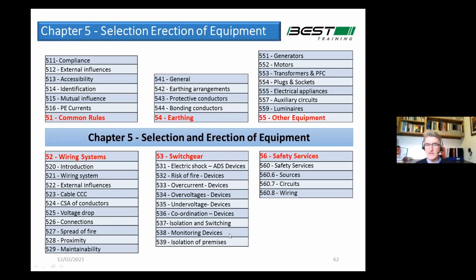53 then is switchgear. So if you look at chapter 53 and read down through there, you'll find it follows almost section by section what we just discussed in chapter 4. So 531 looks at devices for protection against electric shock. 532, devices for protection against fire, such as 300 milliamp RCDs, arc fault detection devices, and so on. 533 deals with overcurrent devices, a direct follow on from part 43. 534, overvoltage devices, undervoltage devices, and so on. So it follows chapter 4 very closely.